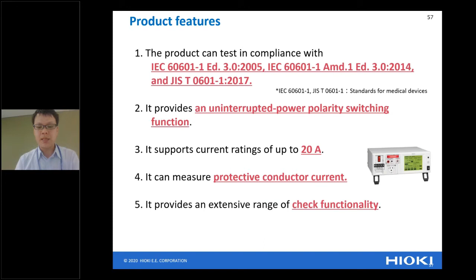Okay, so finally, I want to introduce our ST5540 product features. Of course, the product can test in compliance with IEC 60601-1 edition 3. I already introduced the latest IEC standard. Secondly, it provides an uninterrupted-power polarity switching function. Thirdly, it supports a current rating of up to 20 ampere. Fourthly, it can measure protective conductor current. Finally, it provides an extensive range of check functionality.